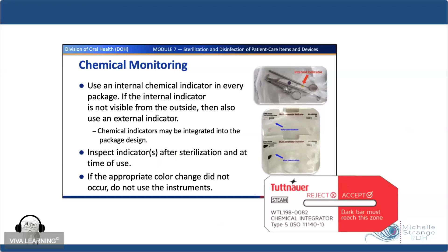And I did write an article about chemical indicators back in 2021 with RDH. You're welcome to go check that out. There are quite a few of them out there, but there are 3 ways to ensure that we are monitoring our sterilizers, and one of them is chemical monitoring. That is done with these chemical indicators. They can be both internal and external, and they use sensitive chemicals to assess physical conditions like the time, temperature, and pressure of your sterilization process. Although chemical indicators do not prove sterilization has been achieved, they allow detection of certain equipment malfunctions, and they can help identify any procedural errors.